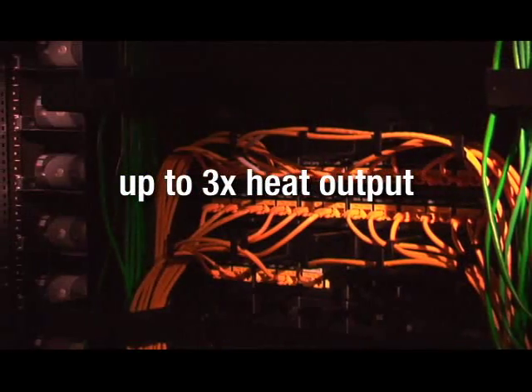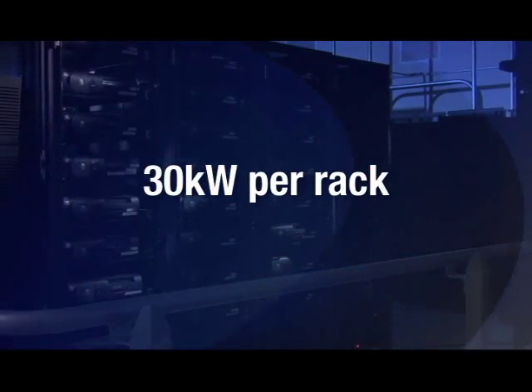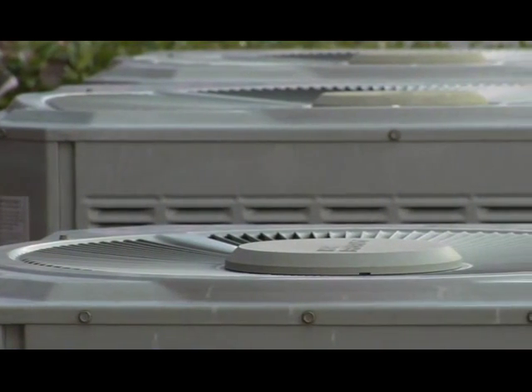And this equipment runs hot, three times hotter than the systems they replace. At even 30 kilowatt per rack, you could need the equivalent of two five-ton air-conditioning units to cool a single rack.